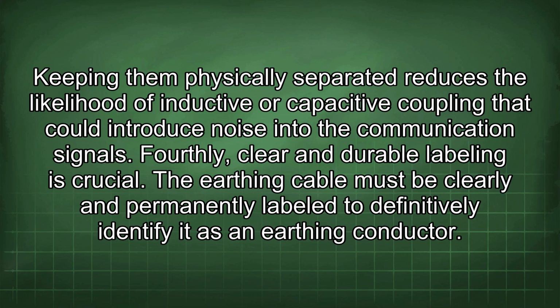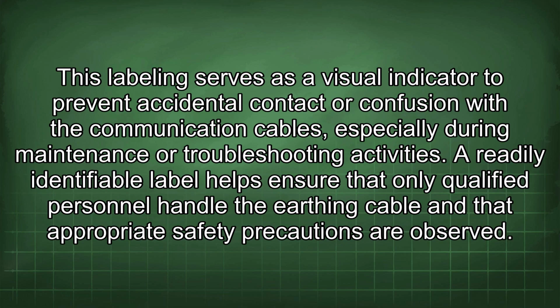Fourthly, clear and durable labeling is crucial. The earthing cable must be clearly and permanently labeled to definitively identify it as an earthing conductor. This labeling serves as a visual indicator to prevent accidental contact or confusion with the communication cables, especially during maintenance or troubleshooting activities.